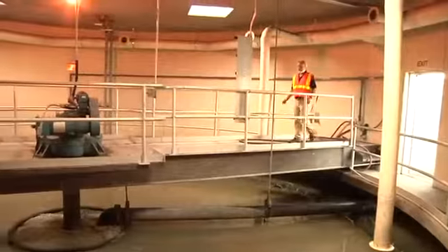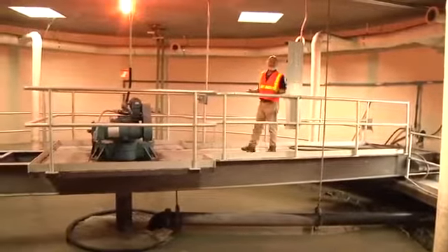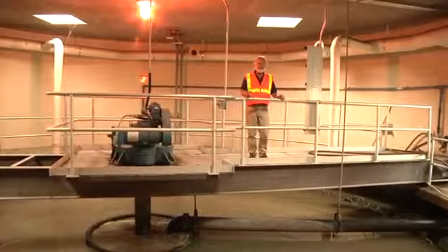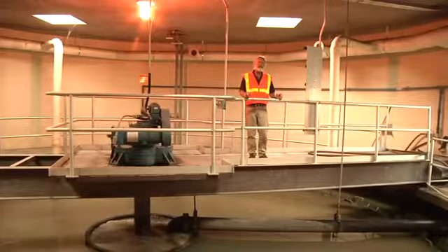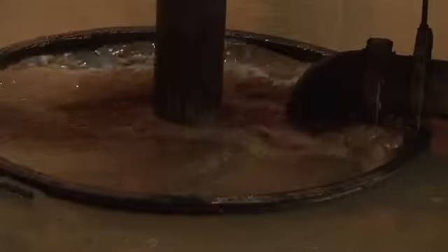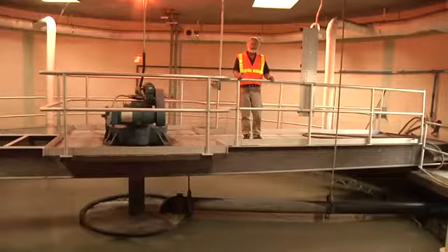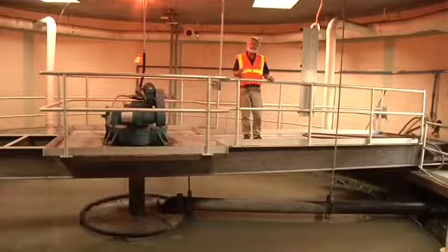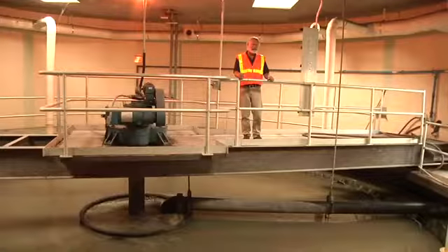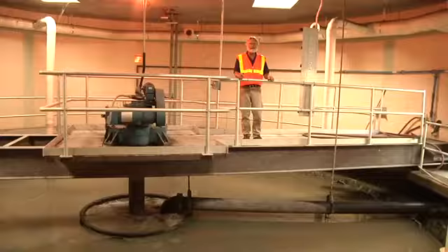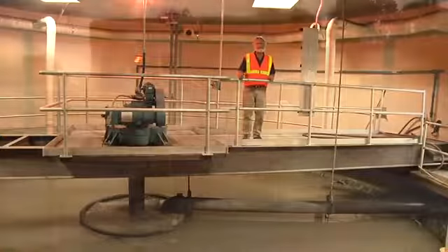This is the sludge thickening process. It's the first step in the solids handling processes, and it's very similar to clarifiers that we looked at before, where we slow the water down and allow the solids to settle out. But the special feature of thickening is that we're taking our solids concentrations from about 0.5% all the way up to 6% solids. The reason we do that is so that we have less energy to pump the solids and so that we have a better treatment in the remainder of the solids handling processes.